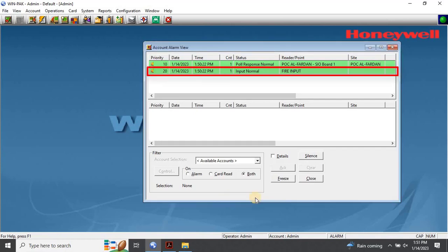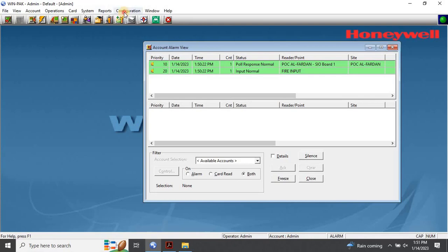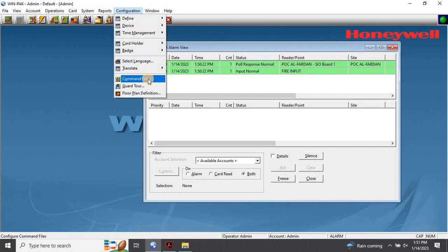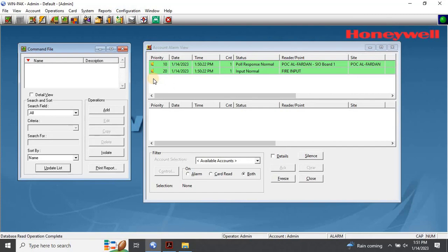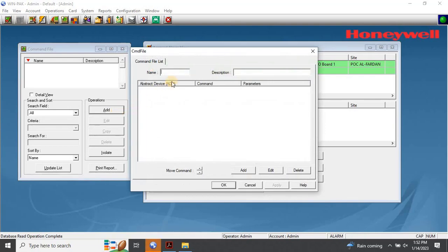The next step is to configure the command file. To do this, navigate to the main menu, click on Configuration, and then select Command File. The Command File configuration window will appear. Click on Add to create a new command file. Enter the command name — for example, Fire Input Door Lock or Door Unlock — and a description. For example, you can create a command file to unlock doors whenever a fire is activated in the building.